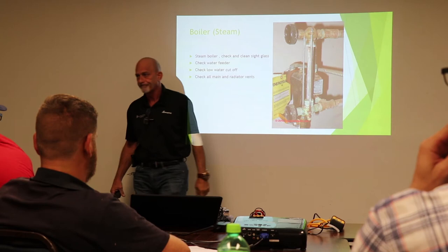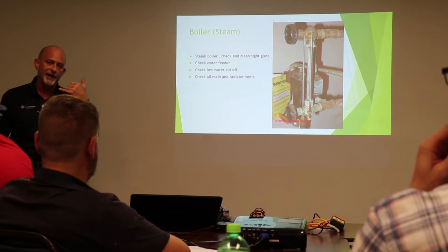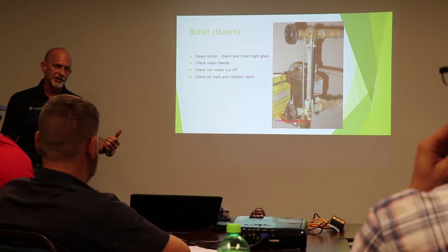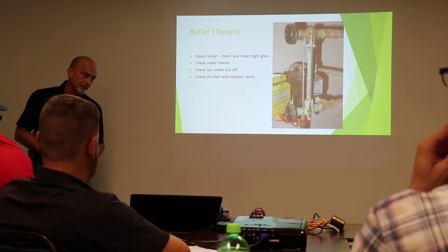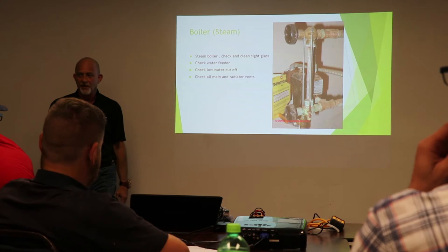Don't be afraid if you break it. You're going to call us up: I need a sight glass for a boiler. Counter guys are going to ask you, do you need a cutter? If you've never worked on steam boilers, you need a cutter. Sight glasses are different sizes. They're not all the same. So you're going to get your sight glass, you're going to get your cutter.